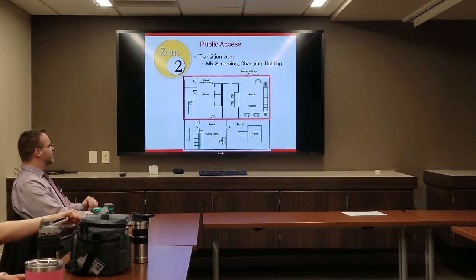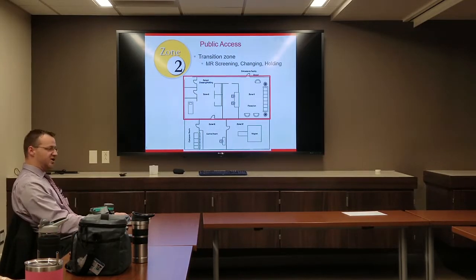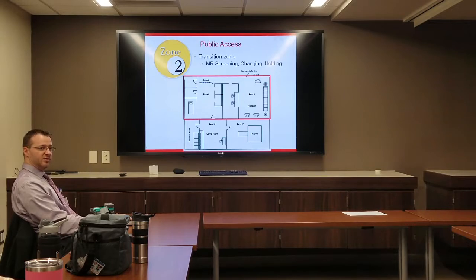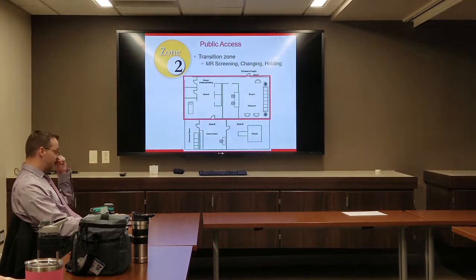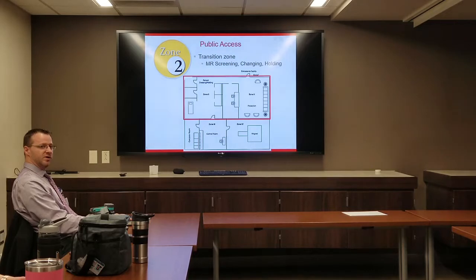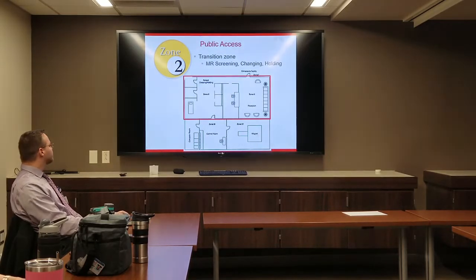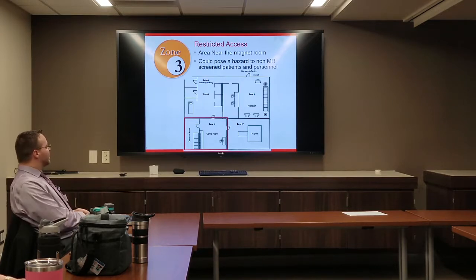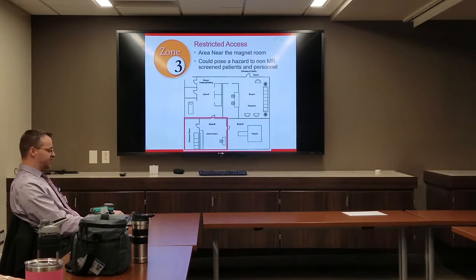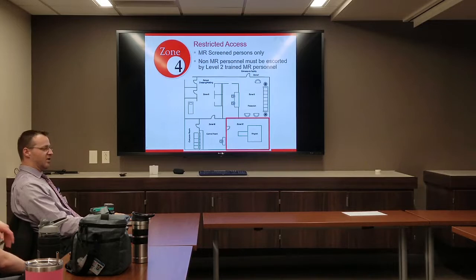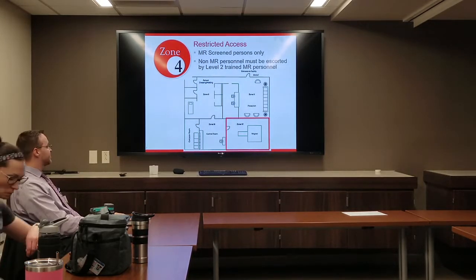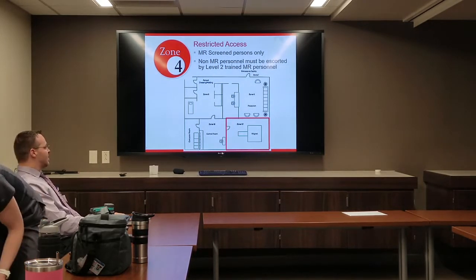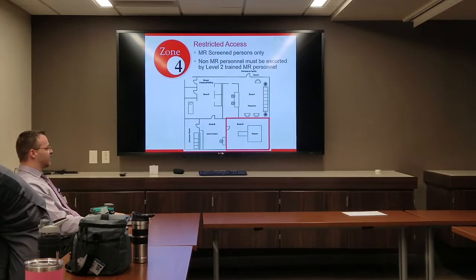Zone 2 is your transition zone — this is where screening, changing, and the holding area for outpatients should be located. Depending on your workflow, inpatient holding might be in Zone 3. Zone 3 is restricted access, near the magnet room, and could pose a hazard to non-MR screened patients and personnel. Zone 4 is the MR room itself, for MR-screened persons only. Non-MR personnel must be escorted by Level 2 trained personnel.